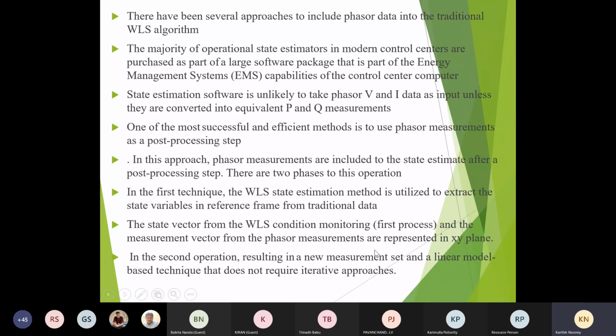So we have said there are major approaches where EMS capabilities can be done, where state estimation is what we have discussed up to now, VI data, unless they are converted into equivalent P and Q measurements. One of the most successful and efficient methods is to use phasor measurements in the post-processing step. That means, first, for bad data selection, they will use state estimation, and later they will append. Appending means adding the state estimation data with the phasor measurement unit data, and they will finally calculate the threshold error. If the error is less than that particular chi square distribution value, then we can say there is no bad data. If it is greater, then we have to calculate the normalized error, with the formulas I have provided there, and then identify that particular bad data, and they have to change that bad data or the meter. Some repair work has to be done at that particular place.